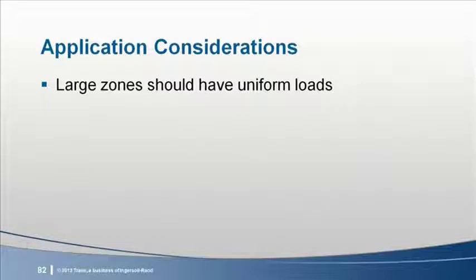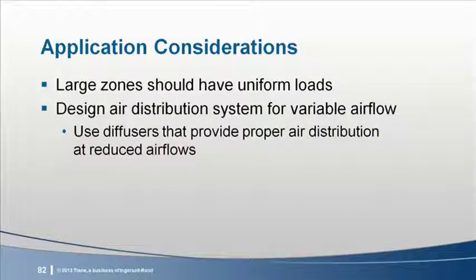Eric? First, the loads throughout the zone need to be fairly uniform. This is a single-zone system responding to a single temperature sensor, so it doesn't have the capability to satisfy simultaneous heating and cooling requirements. If the loads throughout a large zone are not fairly uniform, it may result in undesirable temperature variations in some areas of the zone that are further away from the temperature sensor. This is really no different than for a single-zone constant volume system, where the same challenge can occur in larger zones. Second, design the air distribution system to accommodate variable supply airflow.